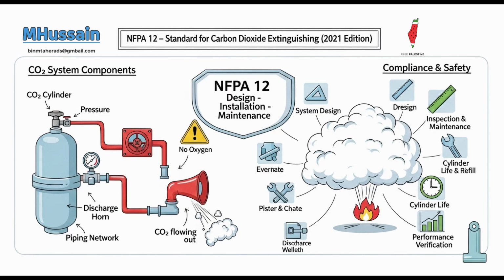The distribution system is where the incredible pressures and extreme cold of CO2 are managed, moving the agent from storage to the point of discharge. The piping must be made of metallic, non-combustible material. Metal pipes, obviously. Capable of predictable performance under immense stress and cryogenic temperatures. Common materials include black or galvanized steel, like ASTM A53 or A106 with their specific steel pipe standards, or stainless steel, TP304 or TP316. Specific types of steel.